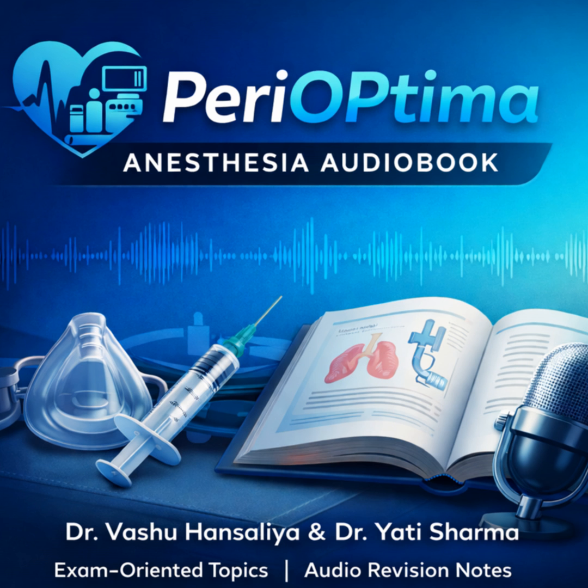What are the main types of autoclaves we need to know? Two main types for your exam. The older type is the gravity displacement autoclave. Steam is pumped in at the top, and because it's less dense than air, it pushes the heavier, cooler air out through a drain at the bottom. It's simple, but it can be slow, and air pockets can get trapped.